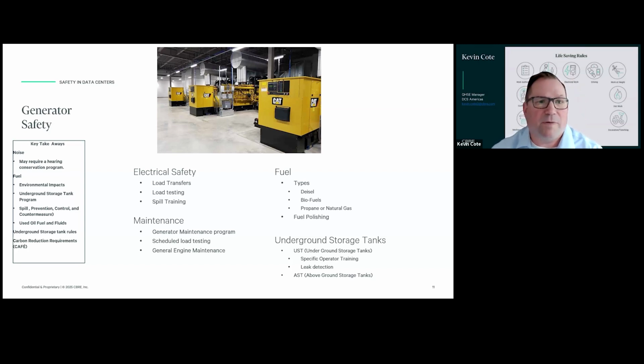So most of the time, fuel is stored either in an above ground storage tank or an underground storage tank. An above ground storage tank is exactly that. It's above ground and just has some really general rules as far as what you have to do for inspections and those types of things. An underground storage tank has a lot more rules, and it really depends on what state you live in. It could even be the city or county that you live in. It depends on what you need to operate an underground storage tank and what their program is.